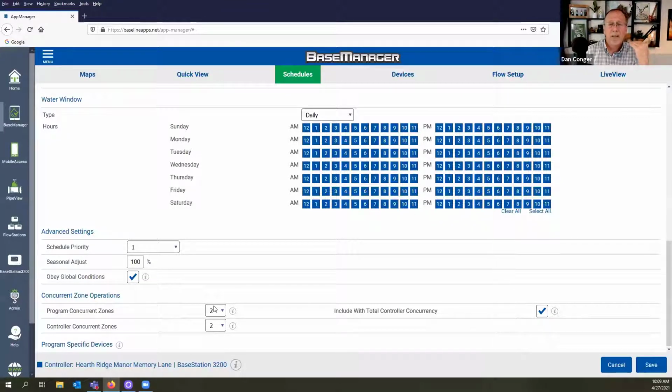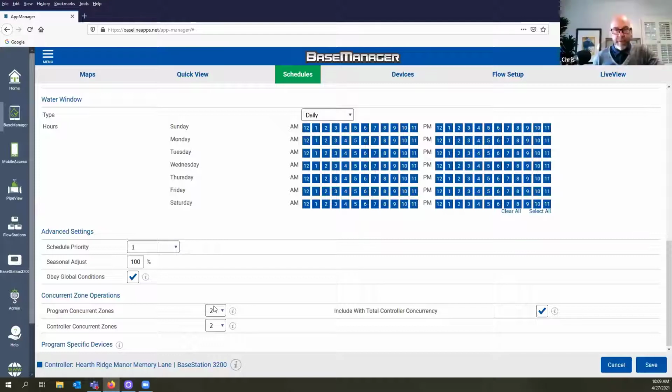I think that is the easiest way to get into this, right? It's not particularly sophisticated, but if you've turned on 2 zones in this grouping, in this program, and they've run fine, then you can run 2 at a time. Yeah. And that's eyes on site, right? Yeah. You've seen those zones operate at the same time, and pressure's good. You're getting the coverage that's desired.